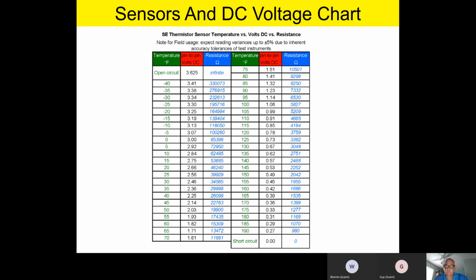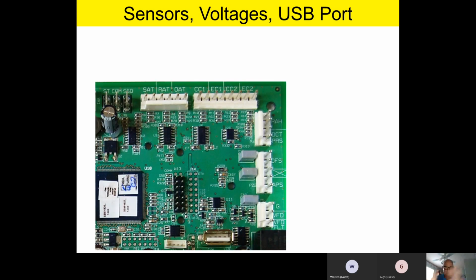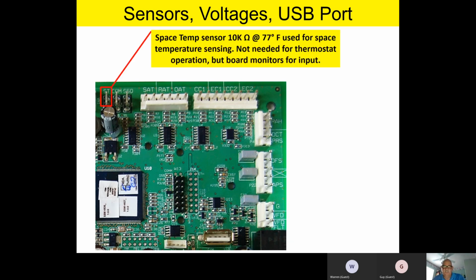Well, let's continue then. So here's that section of the board that we blew up, and now again we're going to talk about some sensors. So you'll see that if I pull those harnesses off, I can actually read the voltage on the sensor inputs, those pins, with my DC voltmeter. Starting at the upper left-hand corner in this section of the board, ST is a space temperature sensor. Now, like all of our temperature sensors that we're going to be talking about, the nominal calibration point is 10,000 ohms at 77 degrees. Please excuse me, I said 75 before, so let me make that quick correction. Space temperature sensor is 10,000 ohms at 77 degrees, not 75.